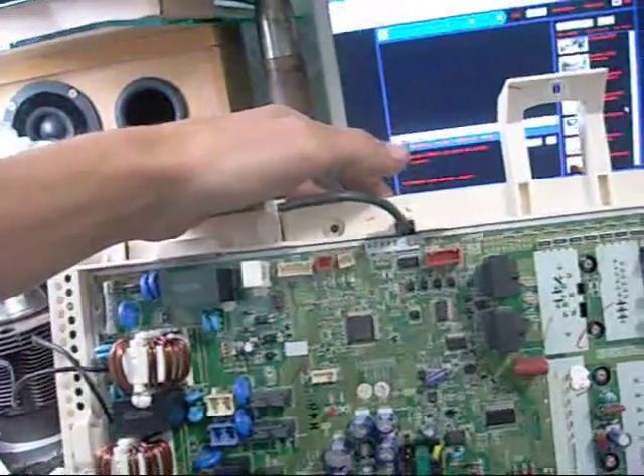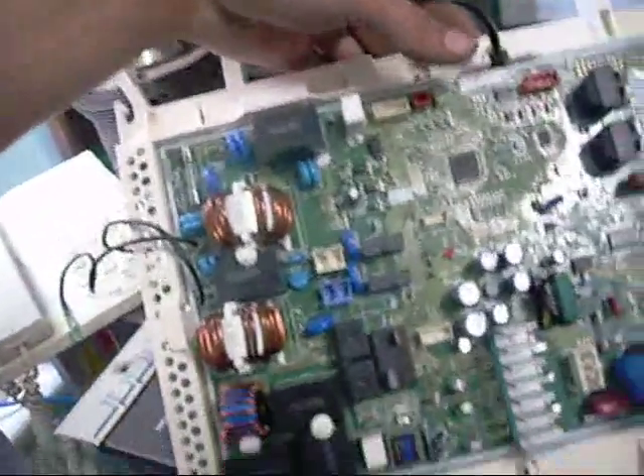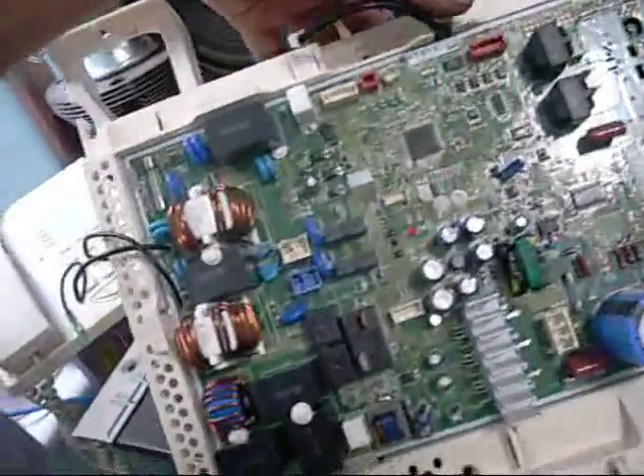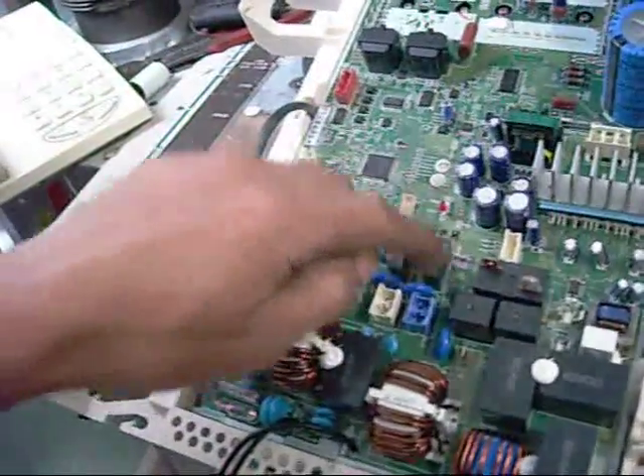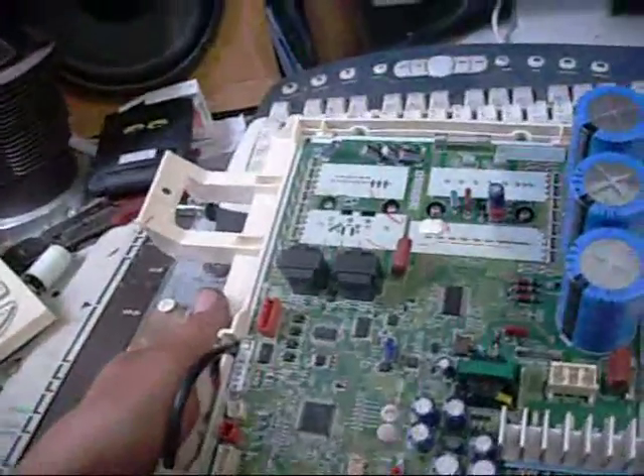Particularly split systems where the condensing unit might have been outside on the ground and gotten flooded, but the water didn't get high enough to affect the indoor unit which is full of sensitive electronics. If it's an inverter, it's probably tough luck - it's probably never going to work again. You get oxide between the pins, river mud in everything. All the relays will be full of it. If it's an inverter, pretty much throw it in the bin. But we'll look at some older style units and hopefully be able to help some of these guys out.